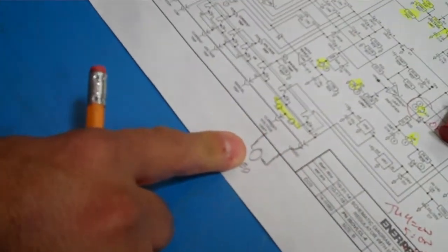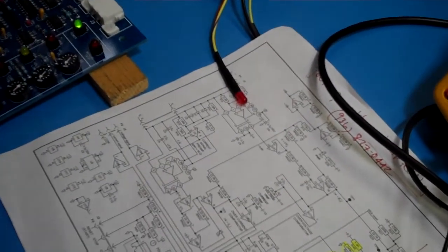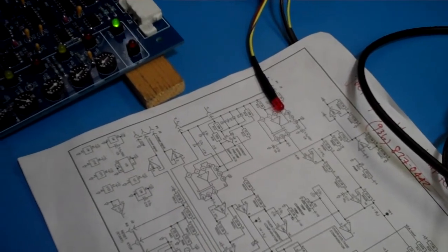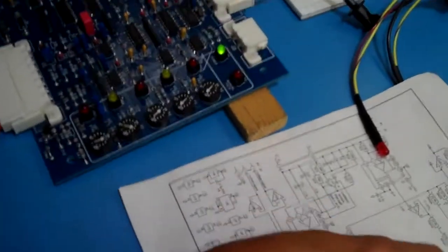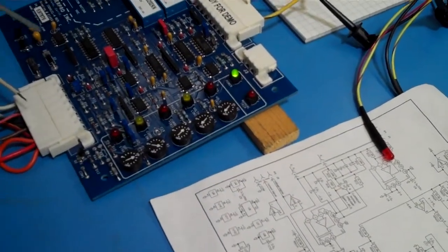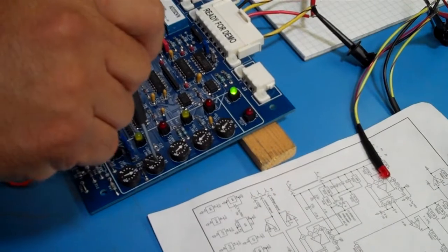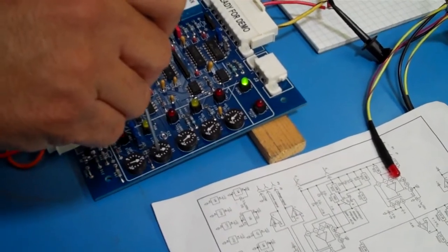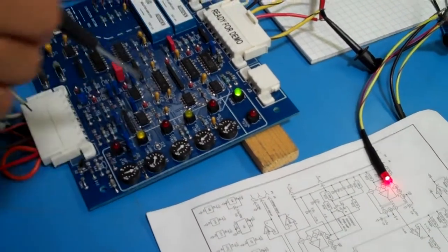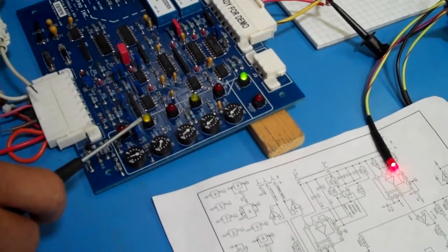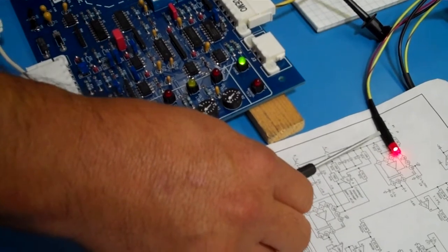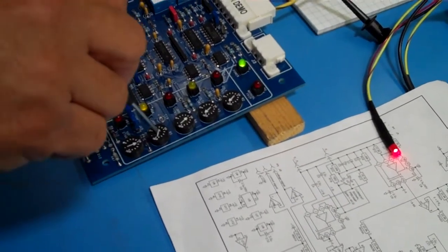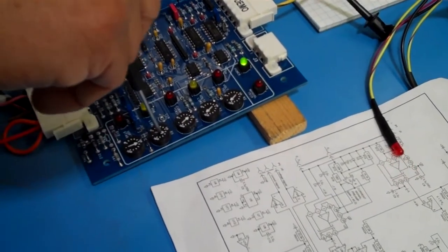JU6 is in, this is connected to 24 volts, and we can see that the LED is off, because the board is not on current limit. Again, we're only interested in current because we're in current limit. So I'm going to go to current limit. I'm going to reduce my command. At that moment I have the current limit LED and that 24 volt LED turned on. Let me clear that again, and that's it, it cleared.